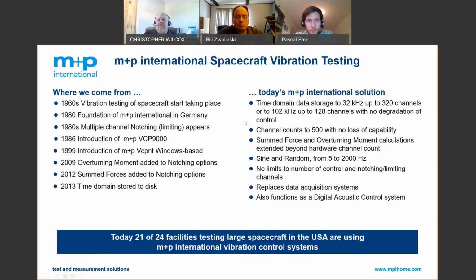Today's latest technology allows up to 102 kilohertz on 128 channels while doing vibration control. We can go up to 500 channels in vibration control with time domain storage, all in the same system. We do force limiting in sine and random out to 2000 hertz. The time domain is attached to the sampling frequency of the control system, so we can sample at 32,000 samples per second when running a sine test to 100 hertz. There are no limits to the number of control channels and notching limit channels, and the force limiting functions I will show you today actually extend beyond your hardware count.